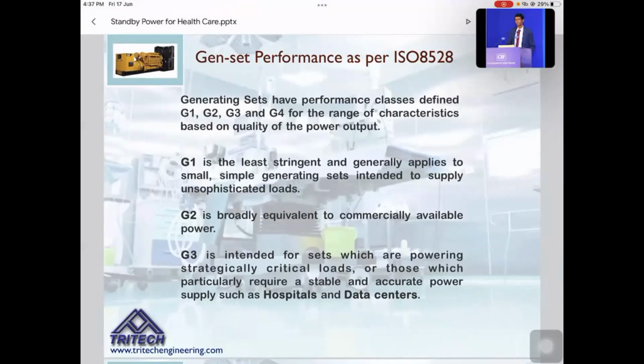And G2 is a commercial generator. So most of the generators you buy are G2 standard, so you don't need to specifically mention that. All smaller capacities are also G2 rated. But G3 rating is required, depending on the specific type and character of the loads, and it is called for only in the case of hospitals and data centers. If you are building a hospital, it is very important that you have G3 rated generator sets, which can handle sudden shock loads without affecting the frequency or voltage while running. This is an important point I wanted to highlight.